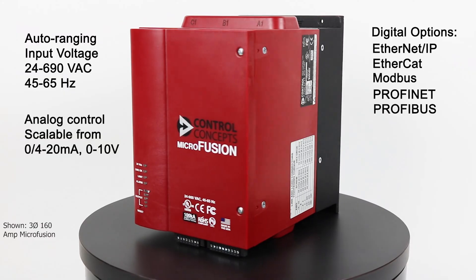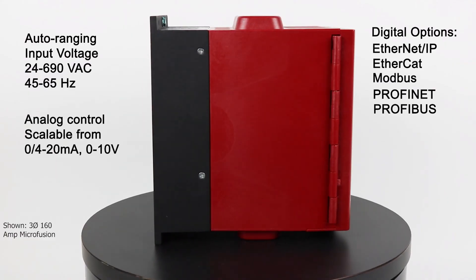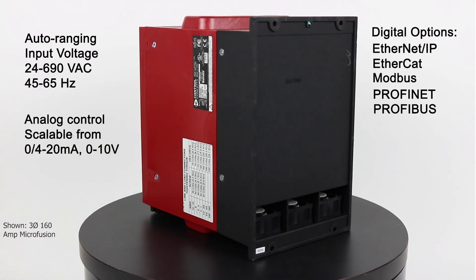Engineers appreciate the flexibility of Microfusion because it can accept either a field scalable analog control signal of 4 to 20 milliamps or 0 to 10 volts, or a digital interface to the PLC such as Ethernet IP, EtherCAT, Modbus TCP, Profinet, or Profibus.